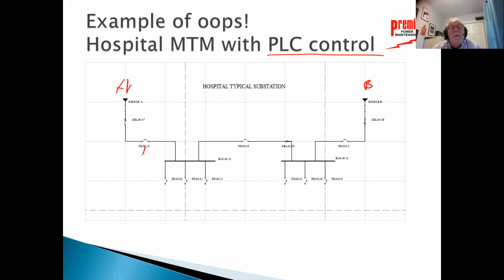And it was so secure that the manufacturer had the foresight to put a UPS system there, so that even if the source died, that UPS would be providing power for that PLC controller. And also that UPS would provide control power for the breakers. It looks like the most secure system in the world. But guess what? When we talk about that single point of failure, the UPS they installed in that system was very similar to one you could buy at one of the big box retail centers for about $99. Well, it wasn't made to last forever. The PLC had some special programming in it. One of the programs says, if we start losing voltage on this UPS, if it starts declining, we want to make sure that we trip all these breakers before they can't trip anymore.